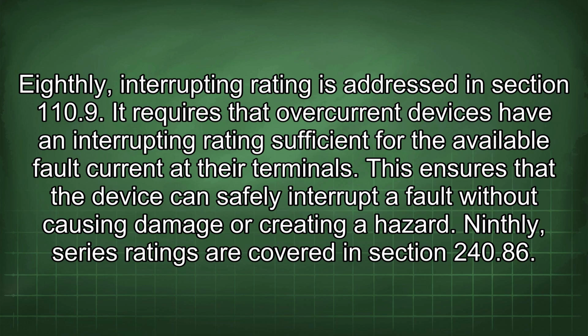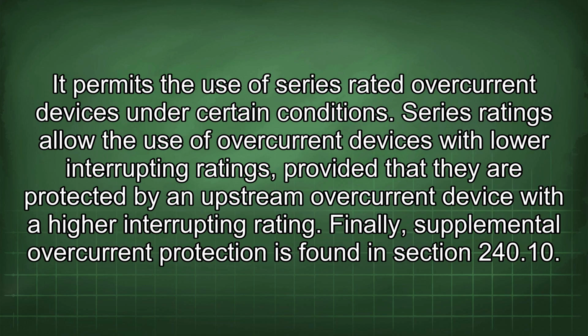Ninthly, series ratings are covered in section 240.86. It permits the use of series-rated overcurrent devices under certain conditions. Series ratings allow the use of overcurrent devices with lower interrupting ratings provided that they are protected by an upstream overcurrent device with a higher interrupting rating.